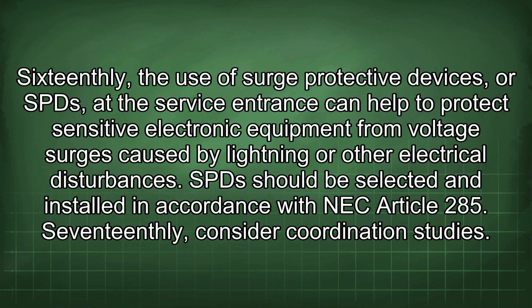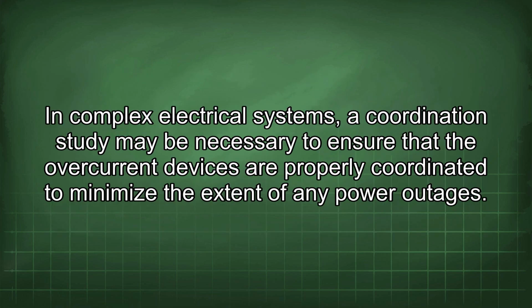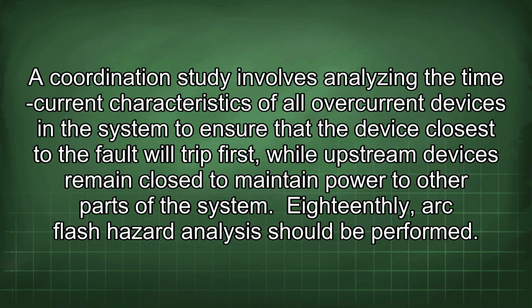17thly, consider coordination studies. In complex electrical systems, a coordination study may be necessary to ensure that the overcurrent devices are properly coordinated to minimize the extent of any power outages. A coordination study involves analyzing the time current characteristics of all overcurrent devices in the system to ensure that the device closest to the fault will trip first, while upstream devices remain closed to maintain power to other parts of the system. 18thly, arc flash hazard analysis should be performed.